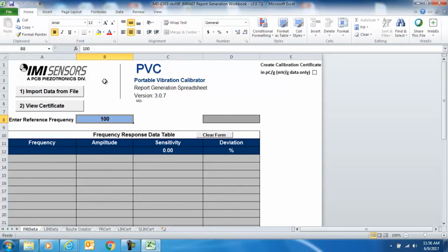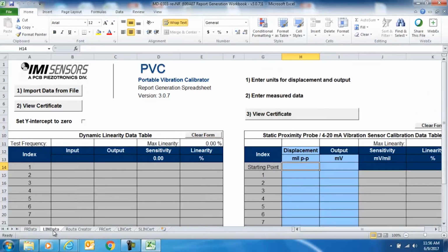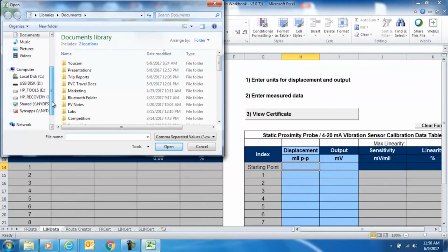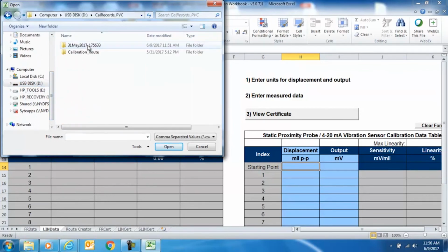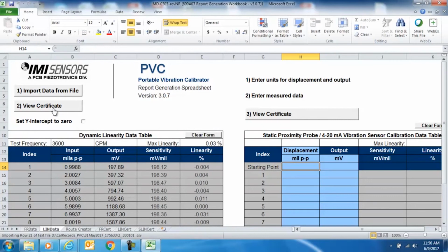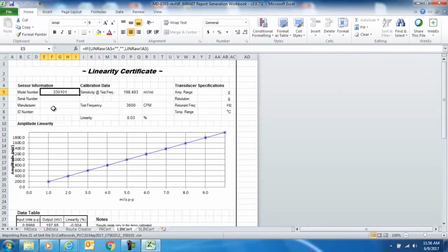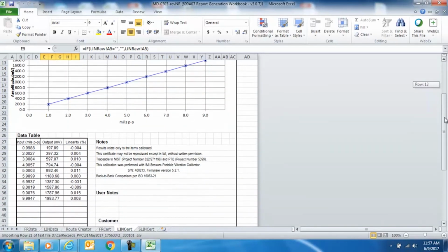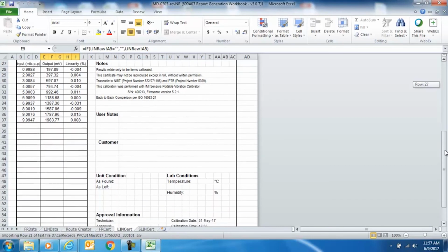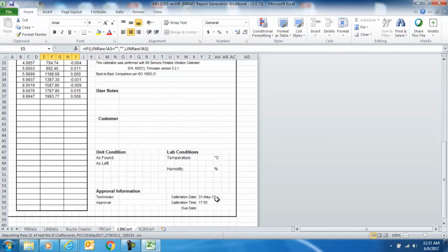From here, for the proximity probe, we did a linearity test, so I want to click on the linearity data tab and then hit import data from file, go back to the USB, open up the Cal records folder and the date that we performed the calibration, and it was the second record, and I will hit open. All of my data has imported. If I press view certificate, you can see my calibration certificate for the proximity probe, my linearity plot from 1 to 10 mils, my sensitivity was 198.5 millivolts per mil at a test speed of 3600 CPM with a maximum nonlinearity of 0.03%. Raw data is found on the data table at the left, and the date and time is automatically inserted into the bottom of the report.